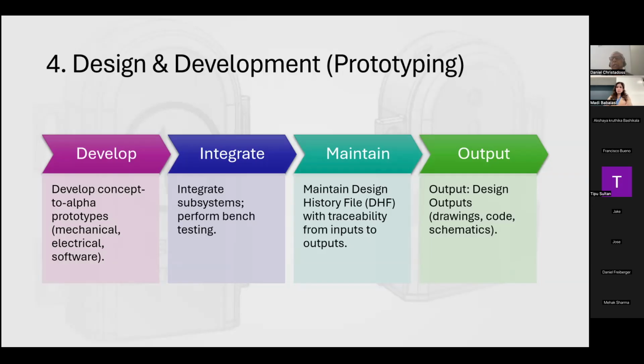They all come together. You may have to do some bench testing on them to see that they meet your requirements. And then you have to maintain what is called a design history file. The FDA is really very keen on this. The design history file, in their mind, if something is not documented, it is not done. So they want you to have a very good history and traceability right from the input stage. So many companies will have what is called a traceability matrix. It's nothing very complicated. All that it says is this particular user requirement, number one, was taken care of in this particular place. So they trace the whole thing.